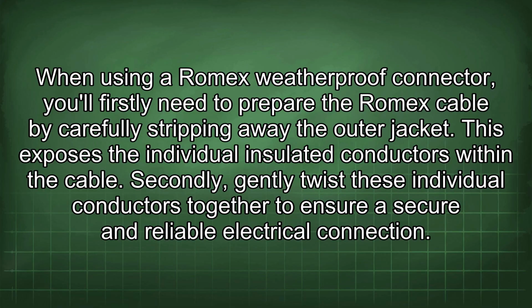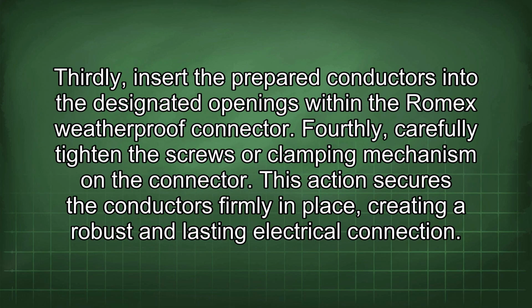Secondly, gently twist these individual conductors together to ensure a secure and reliable electrical connection. Thirdly, insert the prepared conductors into the designated openings within the Romex weatherproof connector. Fourthly, carefully tighten the screws or clamping mechanism on the connector. This action secures the conductors firmly in place, creating a robust and lasting electrical connection.